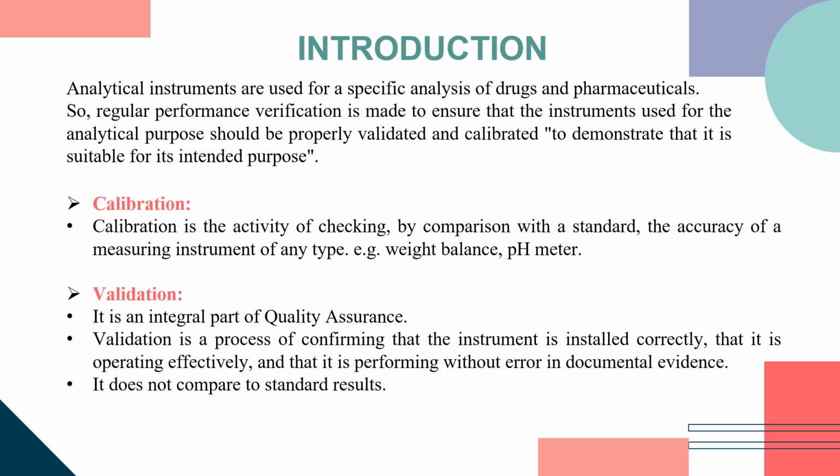On the other hand, validation is an integral part of quality assurance. In the validation process, we check whether the analytical instrument is properly installed or not, and effectively working or not, without error. In the validation process, we do not compare with the standard results.